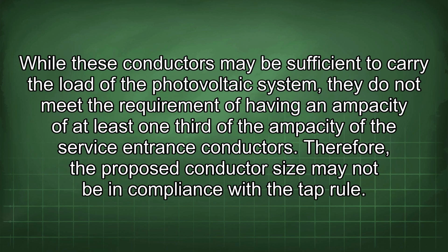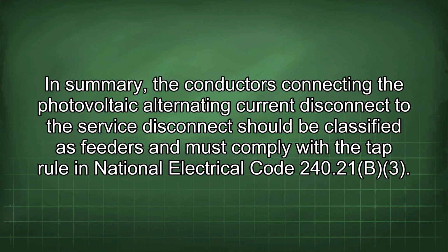While these conductors may be sufficient to carry the load of the photovoltaic system, they do not meet the requirement of having an ampacity of at least 1/3 of the ampacity of the service entrance conductors. Therefore, the proposed conductor size may not be in compliance with the tap rule.